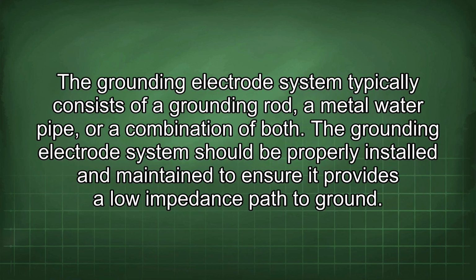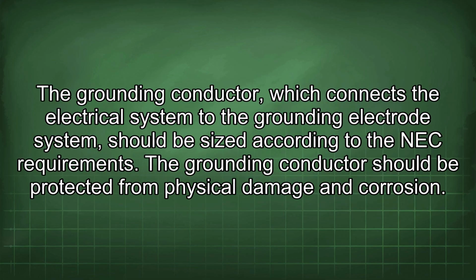The grounding electrode system typically consists of a grounding rod, a metal water pipe, or a combination of both. The grounding electrode system should be properly installed and maintained to ensure it provides a low impedance path to ground. The grounding conductor, which connects the electrical system to the grounding electrode system, should be sized according to the NEC requirements. The grounding conductor should be protected from physical damage and corrosion.